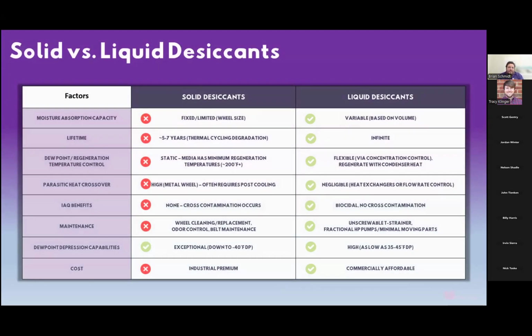Really quick, I want to compare solid and liquid desiccants. They both have their advantages and disadvantages. But some of the factors that I want to discuss are more moisture absorption capacity. A solid desiccant, this is more fixed. It's based on the wheel size. Whereas I mentioned before, liquid desiccants, it's variable. It depends on the concentration of the liquid desiccant itself. The lifetime, as I mentioned before, liquid desiccants, we can cycle infinitely, versus solid desiccants do have a limited lifespan.